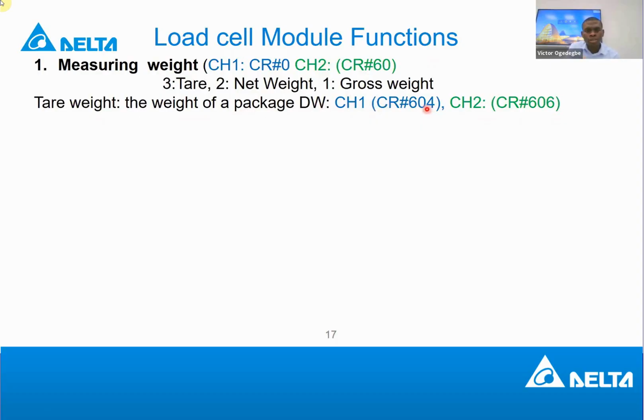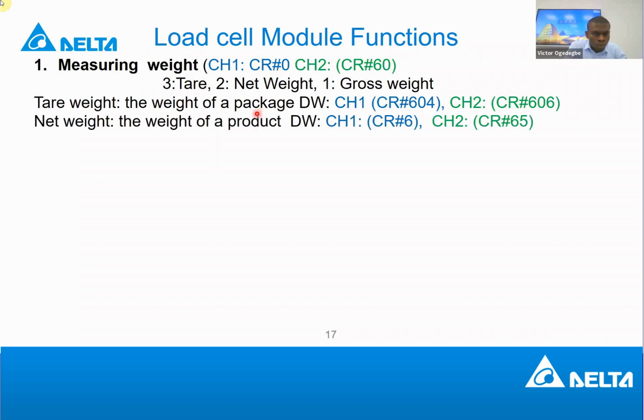Another thing that's also very interesting is that you can set a tare weight. You can set a digital value such that if you read this digital value from the sensor, this digital value is my tare weight. It means the weight of a package, when there is no load on the load sensor, the weight of the empty bucket. Another weight is the net weight. The net weight is the weight of the product. Here you can get the net weight of what should be measured. Channel 1 is double word. Channel 1 is 6. Channel 2 is 65.